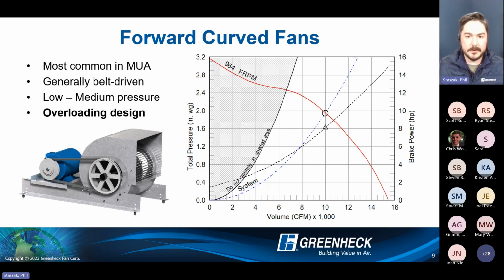Obviously, that's not going to be the case every time, but if you don't have any ductwork hooked up to these systems, say even if you have a factory provided 3-way or 4-way diffuser, as a manufacturer, we calculate that static pressure into the system already. So if that system is ordered at 10,000 CFM for a through wall design, where the weather hood is just extruded on the outside of the unit and we're just throwing air into that building, we want to make sure to lay out that system at 0 inches of external static pressure because there's nothing else for the unit to overcome.